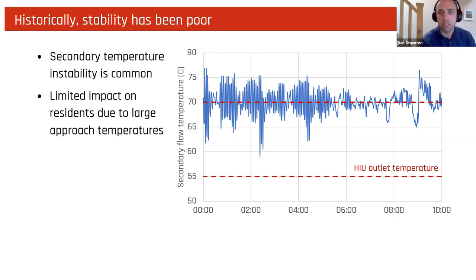As demand starts to increase, past 6 o'clock onwards, we start to see slightly more stable operation, but still fluctuating between 75 and 65 degrees. Historically, this has had a relatively limited impact on residents. We've designed with relatively large approach temperatures between secondary flow temperatures and HIU outlet temperatures. So in the scheme this was taken from, whilst the plate was delivering at 70 degrees, the HIU was only delivering 55 degrees to residents. The plate could therefore vary around 10, 15 degrees from set point without any impact on residents.